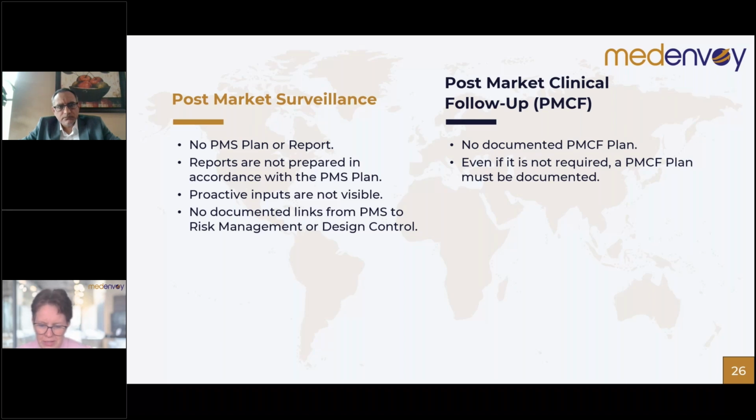And the issues identified were, for example, no PMS plan in place, or the procedure lacking certain elements, so not fully complying to MDR requirements. But the majority of the cases related to the contents of the PSUR, where they clearly identified, similar to what you already stressed, that we need to include sales volumes. The patient population in use? Was that in scope, out of scope? Is the frequency of use within the expectations? Results from CAPA, etc. So we see more and more oversight from competent authorities, and so paying attention to the process of post-market surveillance is indeed important, I think.